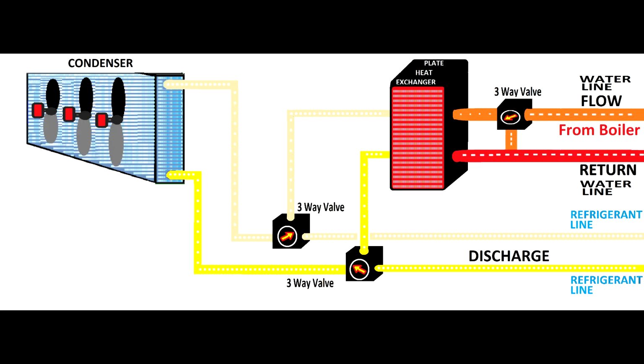Best will be to push water at 20 degrees or 18 degrees and to take it out at a temperature of 45 degrees. But if you have an incorrect plate heat exchanger or an unbalanced system, you might have a ratio of 10 degrees. So you push 10 and the water goes, as an example, to 20. So that's why the boiler should push 30 into this plate heat exchanger, and the plate heat exchanger will boost it to 45. So if you're not balancing the system very well, you will see this type of phenomenon.